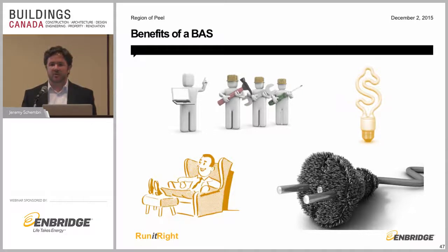It allows us to do some troubleshooting in advance of bringing in an external vendor to work on it, so that we can help hone in on that scope of work. It also lets us look at things when sometimes it's just competing systems, and our BAS will let us find that out. Not all of our systems, unfortunately, in all our facilities are on our BAS. So if we have an electric baseboard heater in an office that could be competing with our central forced air system, that can start to become a problem, which will start to trigger the BAS and have that conflict. Through troubleshooting with our system, we can find those problems and address them rather than bring in a vendor and spend a lot of money that might not be necessary.